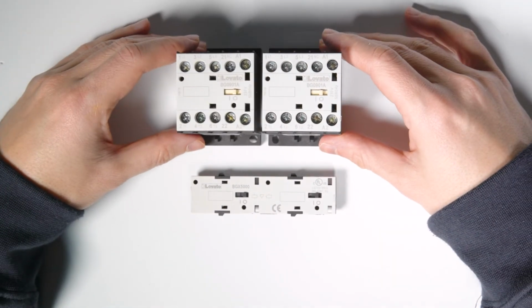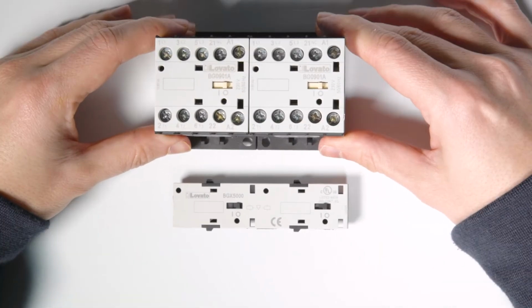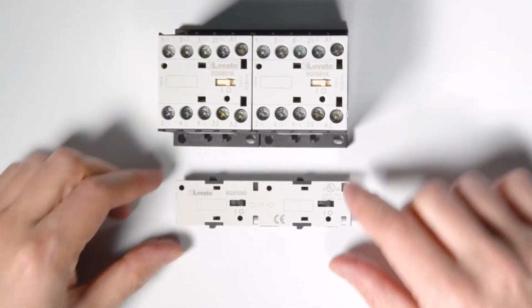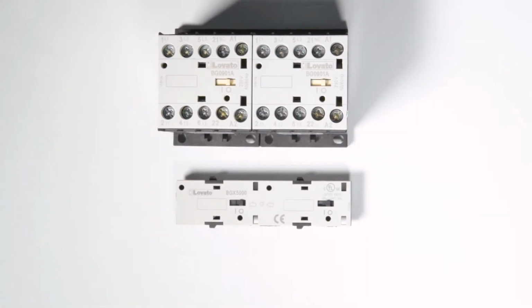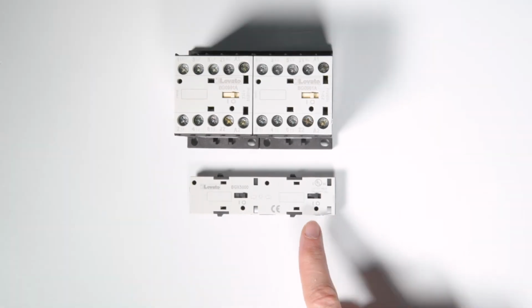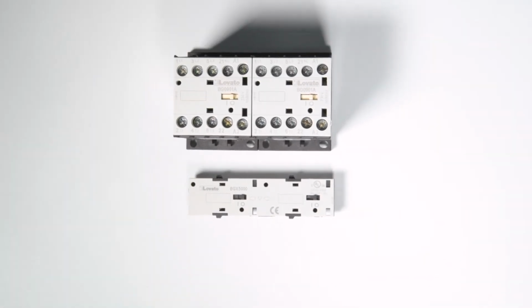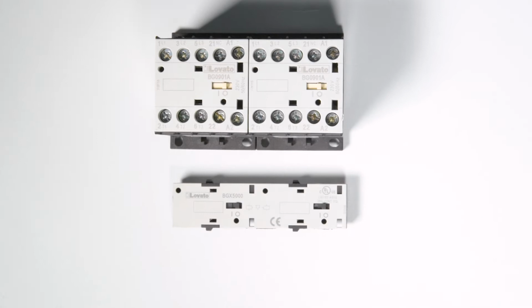Now, put the two contactors side by side and line up the pins so that they enter all the way. Before fitting the mechanical interlock, remember to position it on zero so both the interlock sliders are in the open position. This is very important.